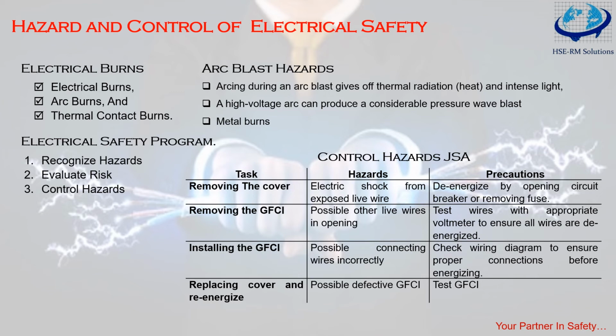Now, the path of the ground may be missing or disconnected. If you have earth provision for each equipment and panel, then ensure that its continuity is checked and proper checks are done when testing earth pits. Earth continuity for the path or earth should also be connected. How to do it? Simple: have provisions for checking continuity.